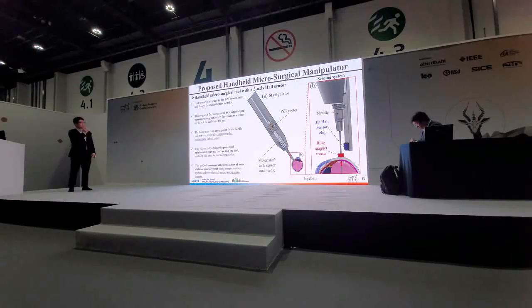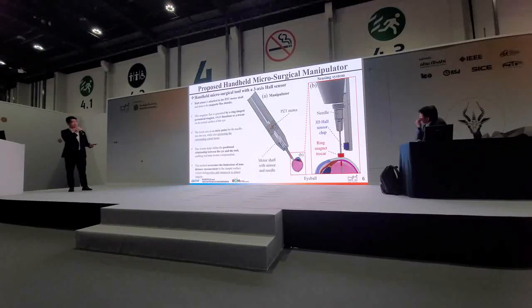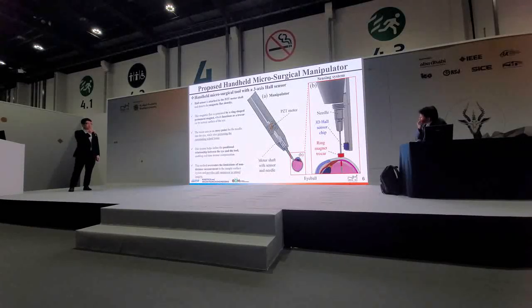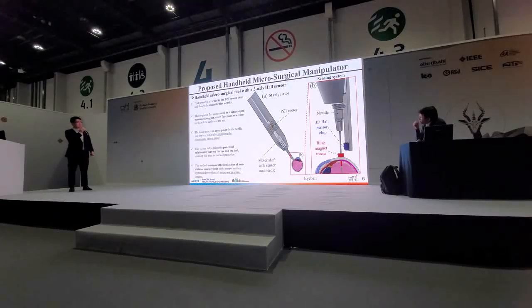Our proposed study introduced a handheld microsurgical tool with a 3-axis Hall sensor. Hall sensor is attached to the PZT motor shaft and detects the magnetic flux density. This magnetic flux is generated by a ring-shaped permanent magnet which functions as a trocar on the scleral surface of the eye. The trocar acts as an entry point for needle into the eye while also protecting the surrounding scar tissue. This system has defined the positional relationship between the eye and the tool, enabling real-time tremor compensation. This method overcomes the limitation of non-distance measurement to sample surface system and provides safe maneuver in retinal surgery.